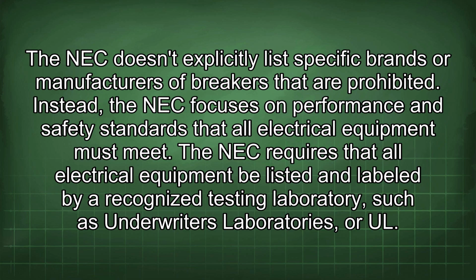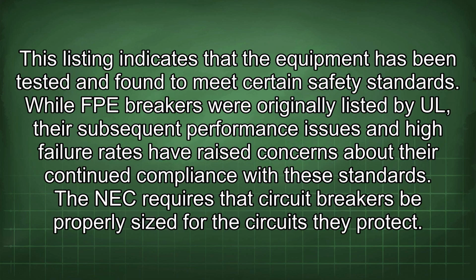The NEC doesn't explicitly list specific brands or manufacturers of breakers that are prohibited. Instead, the NEC focuses on performance and safety standards that all electrical equipment must meet. The NEC requires that all electrical equipment be listed and labeled by a recognized testing laboratory, such as Underwriters Laboratories. This listing indicates that the equipment has been tested and found to meet certain safety standards. While FPE breakers were originally listed by UL, the subsequent performance issues and high failure rates have raised concerns about their continued compliance with these standards.